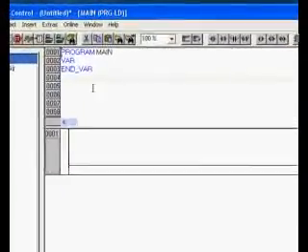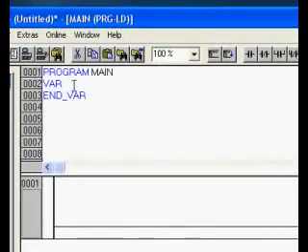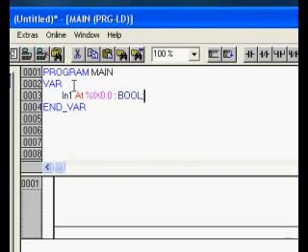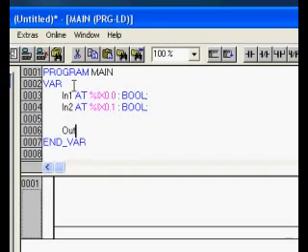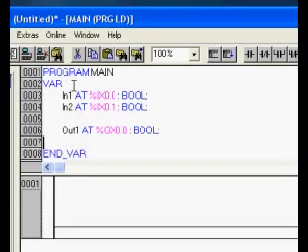Okay, so now the very first step, I'm going to create some variables. TwinCAT is tag based, so I'm doing this manually. You can do a table if you want. So what I'm typing, I'm creating variables and declaring an address. Now these addresses are just addresses I've made up to use, and you need to do that whenever you're going to link physical I/O. And in order to run TwinCAT, you have to have what's considered a sync master, which is at least one physical I/O. So that's why I'm just going to declare 2 inputs and 2 outputs.